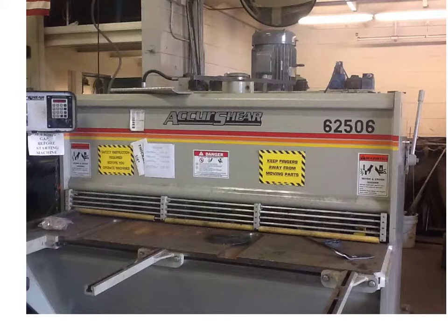This piece of equipment is a shear. This is something a welding shop would use to actually cut large pieces of metal. And up here at the top you'll see there's a pretty substantial AC motor. This is a pretty common project for us as electricians. We have to come in and analyze the information we've got. We've got this motor, and we've got to get a branch circuit run over to this shear. So we've got to look at the nameplate of the motor and make some determinations.